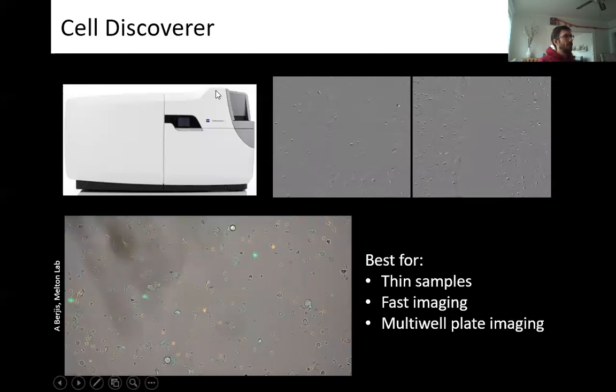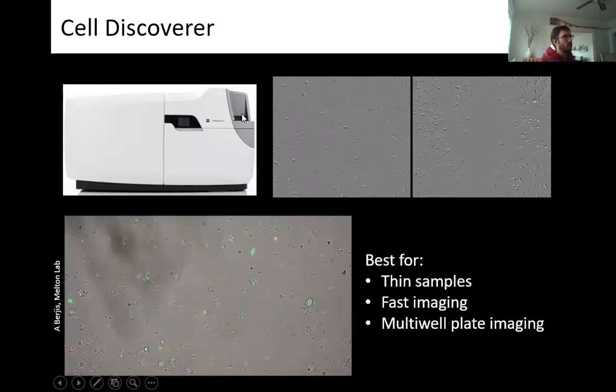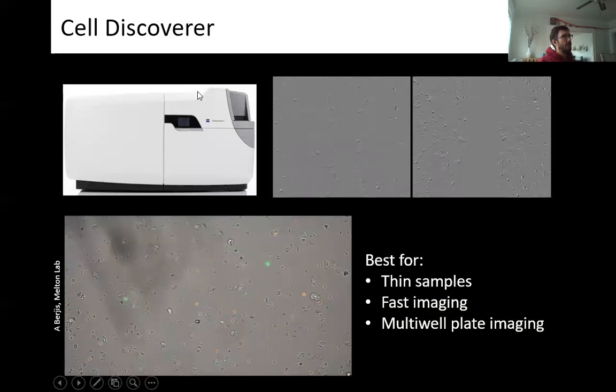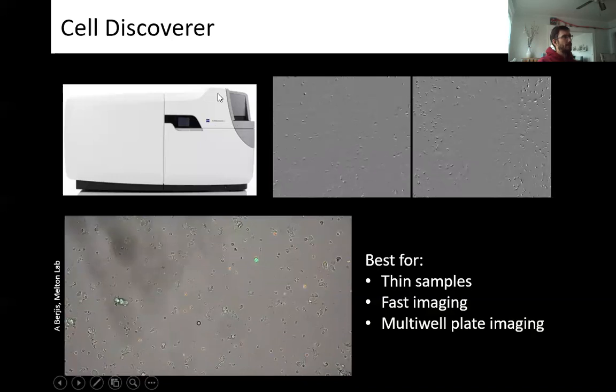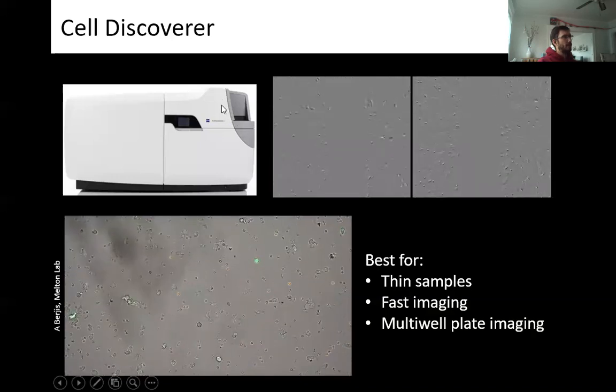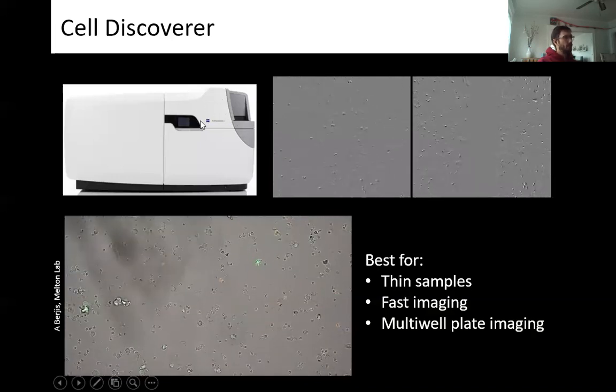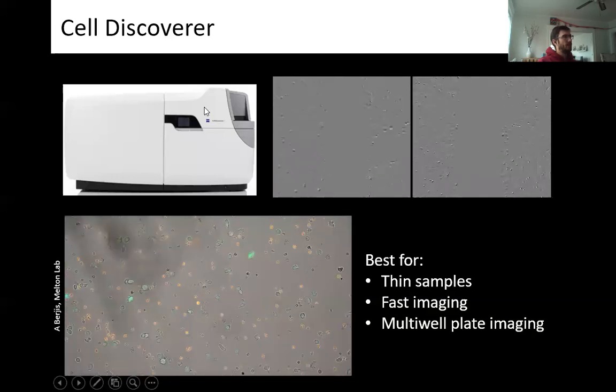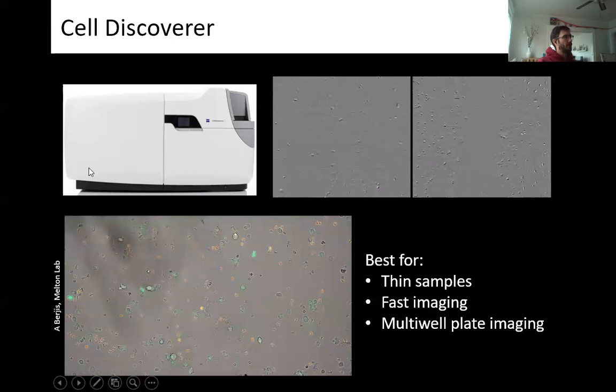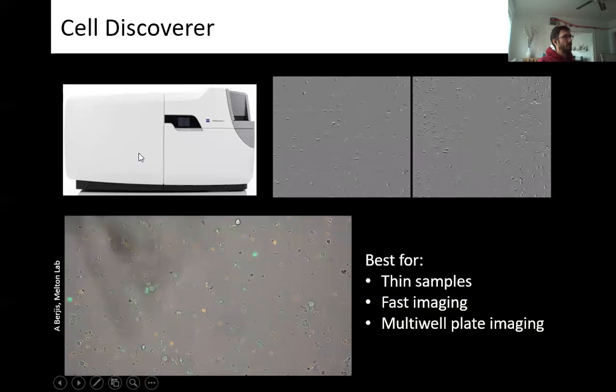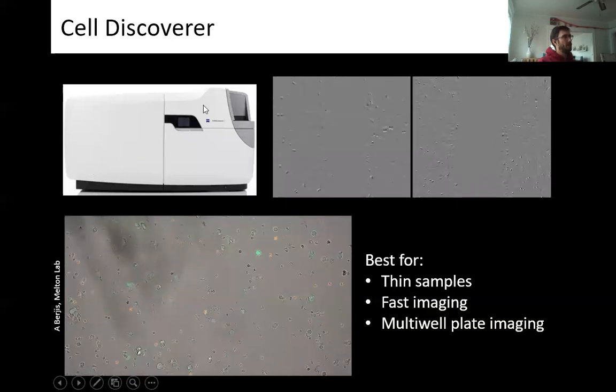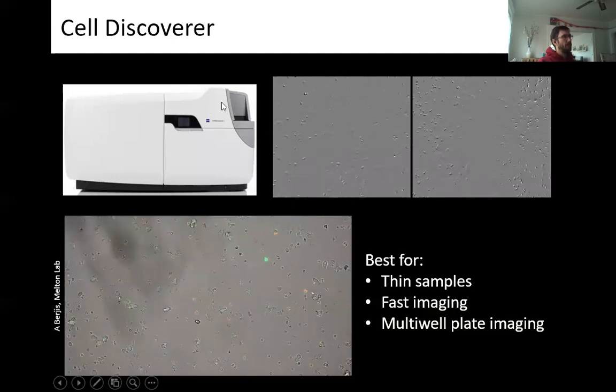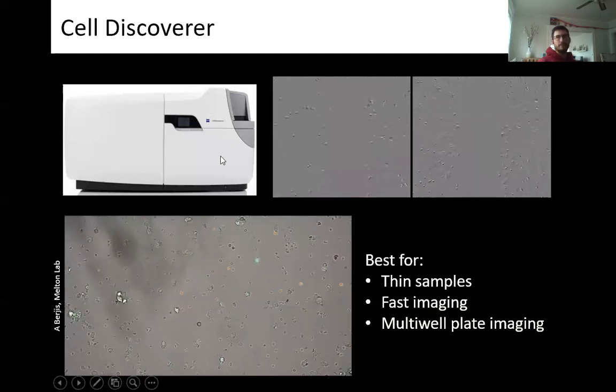Inside the Cell Discoverer, you put your plate or sample in, it's taken into a fully environmentally controlled chamber at the back — heated, with humidified air supplied by a water bottle, and CO2 mixed in over the sample as well. Very easy to keep samples nice and happy in here.